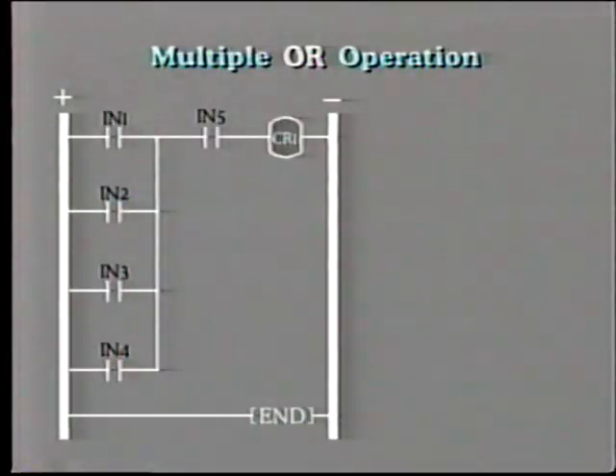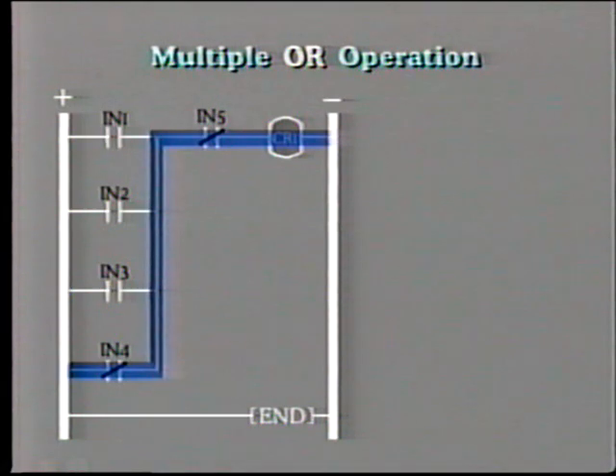Let's look at another example. In this case, a multiple OR operation. The logic diagram shows that the control relay will be energized when any one of the input contacts, IN1, IN2, IN3, or IN4, are closed, providing that contact IN5 is also closed.